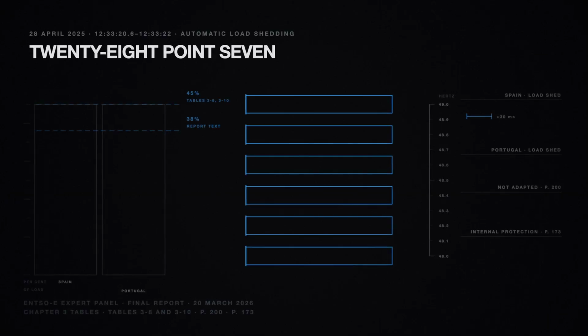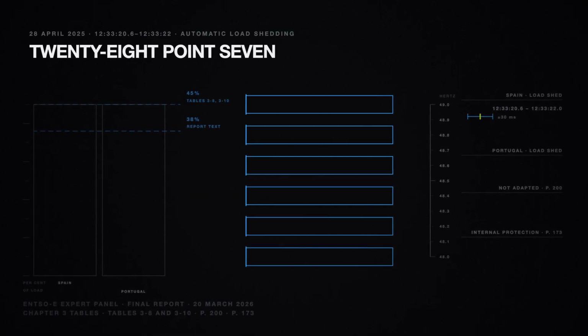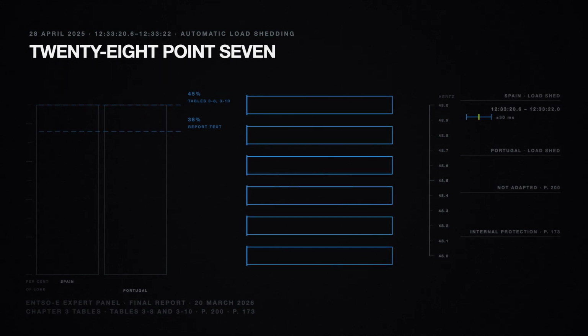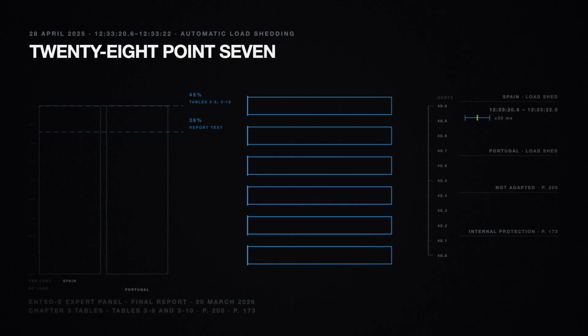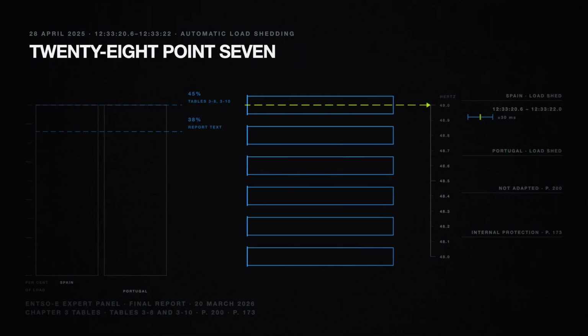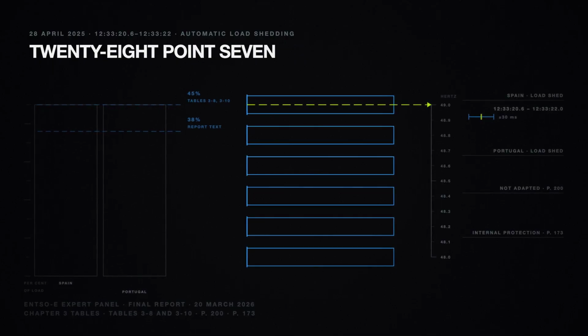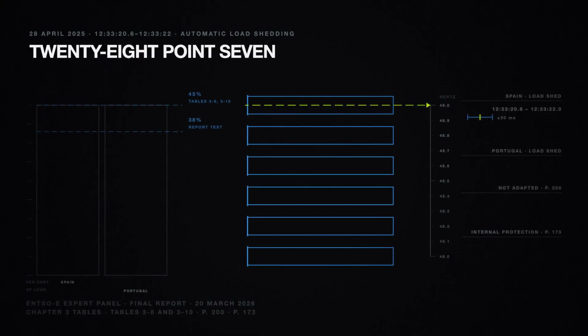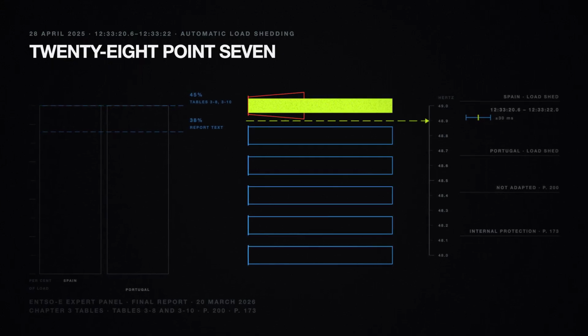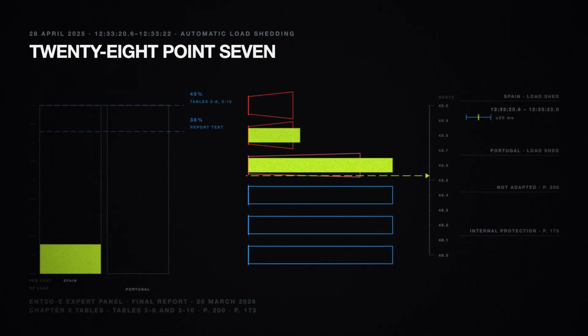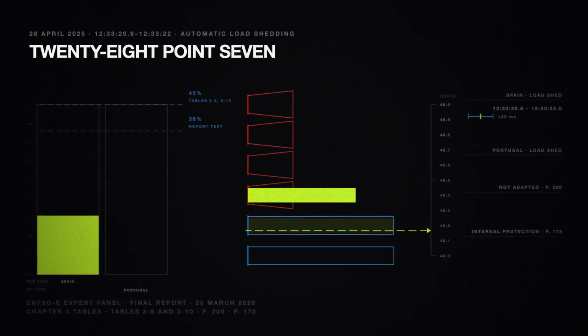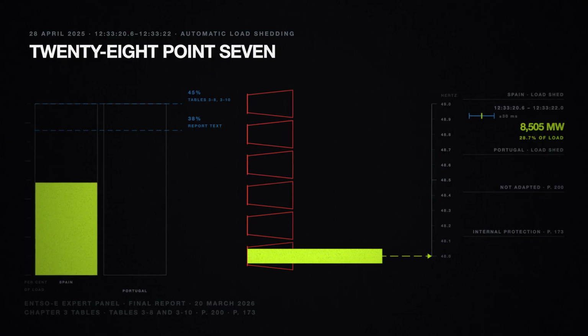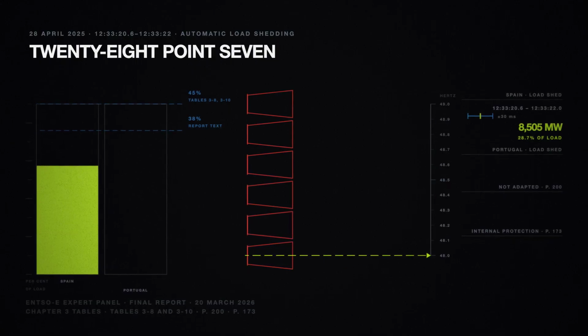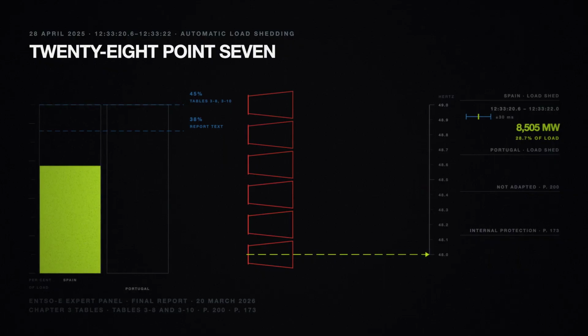Between 12:33 and 20.6 seconds and 12:33 and 22, 6 steps of automatic load shedding opened in Spain. This is the last line of the defense plan. Relays watch frequency, and at set levels they disconnect blocks of demand to hold what is left. The 6 steps ran from 49.0 Hz down to 48.0. Spain shed 8,505 megawatts, 28.7% of its load. The plan asks for more than that, and the report gives the target twice.